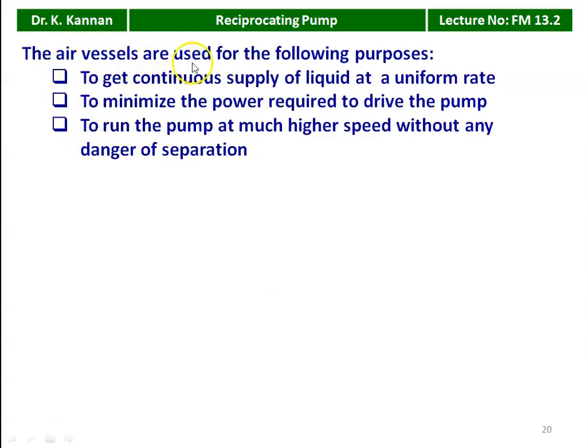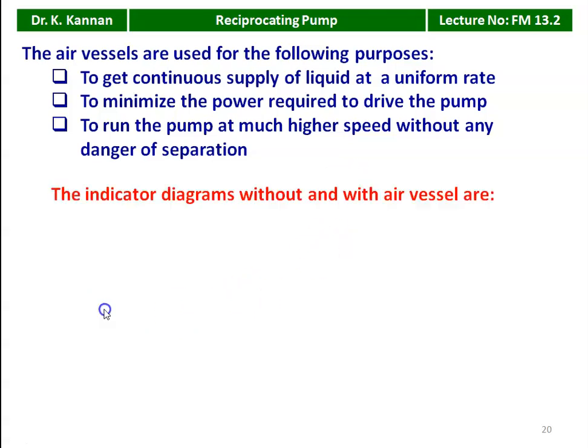Air vessels are used for the following purposes: to get a continuous supply of liquid at a uniform rate; to minimize the power required to drive the pump; and to run the pump at a much higher speed without any danger of water separation. Water separation is a major type of loss in any pump, and it will not happen when you have an air vessel on the suction and delivery side.